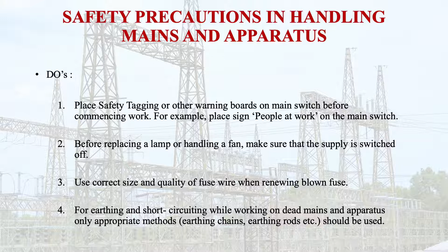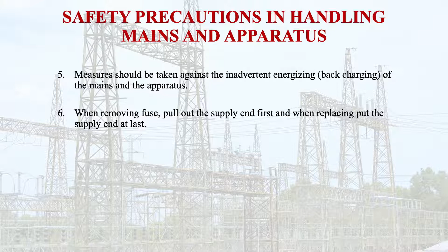Measures should be taken against the inadvertent energizing, that is back charging, of the mains and the apparatus. When removing the fuse, pull out the supply end first, and when replacing, put the supply end at last. It's very clear to you, I think. That means when you are removing the fuse, pull out the supply end first. Okay, and when you are replacing, put the supply end at last.